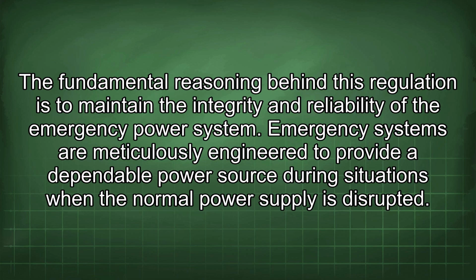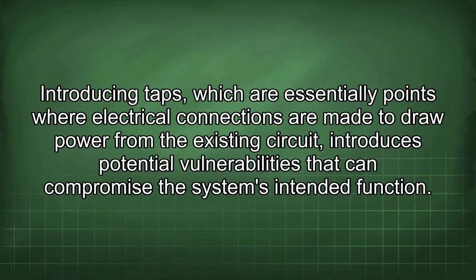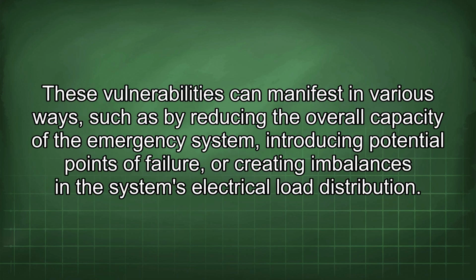Emergency systems are meticulously engineered to provide a dependable power source during situations when the normal power supply is disrupted. Introducing taps, which are essentially points where electrical connections are made to draw power from the existing circuit, introduces potential vulnerabilities that could compromise the system's intended function. These vulnerabilities can manifest in various ways, such as by reducing the overall capacity of the emergency system, introducing potential points of failure, or creating imbalances in the system's electrical load distribution.